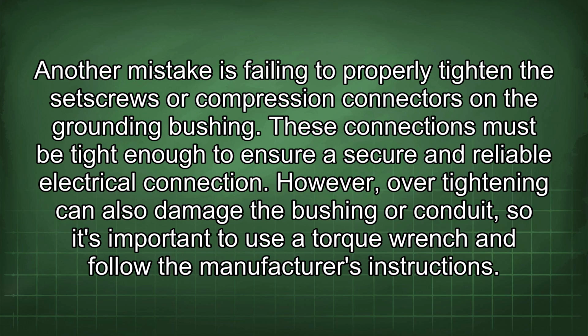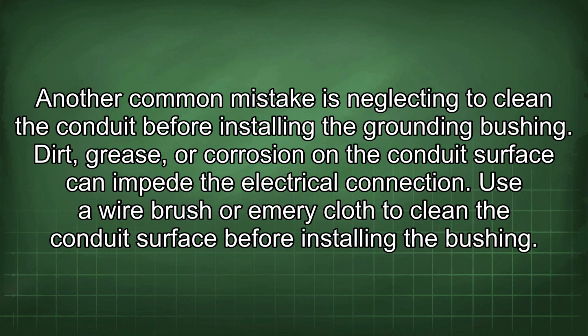However, over-tightening can also damage the bushing or conduit, so it's important to use a torque wrench and follow the manufacturer's instructions. Another common mistake is neglecting to clean the conduit before installing the grounding bushing. Dirt, grease, or corrosion on the conduit surface can impede the electrical connection. Use a wire brush or emery cloth to clean the conduit surface before installing the bushing.